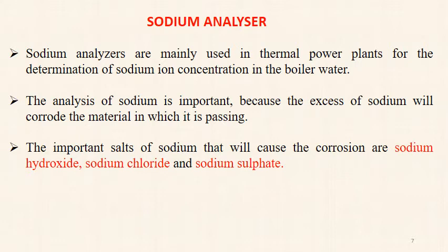Sodium analyzer. The water quality is critical to the efficiency and the performance of a steam generation plant and its associated equipments. Today, sodium concentration has become one of the most important index for water quality throughout the steam and water cycle in power plant. The measurement of sodium in steam before the superheater is a strong indication of possible corrosion in the superheater.